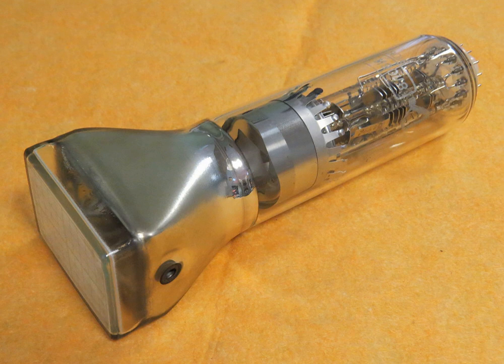In general, for routine use, an open wire test lead for connecting to the point being observed is not satisfactory, and a probe is generally necessary. General-purpose oscilloscopes usually present an input impedance of 1 megohm in parallel with a small but known capacitance such as 20 picofarads. This allows the use of standard oscilloscope probes. Scopes for use with very high frequencies may have 50 ohm inputs. These must be either connected directly to a 50-ohm signal source or used with Z0 or active probes. Less frequently used inputs include 1 or 2 for triggering the sweep, horizontal deflection for XY mode displays, and trace brightening, darkening, sometimes called Z-axis inputs.